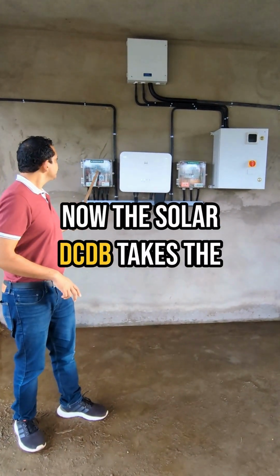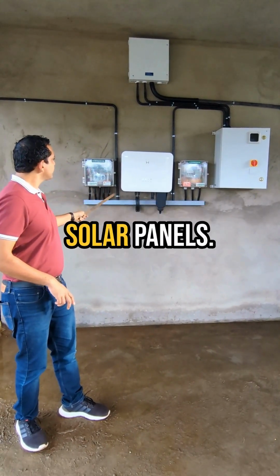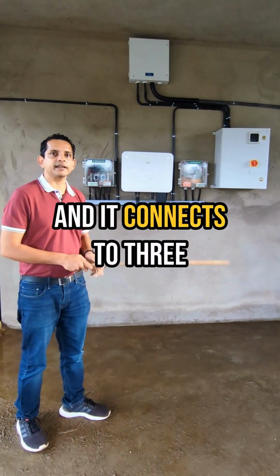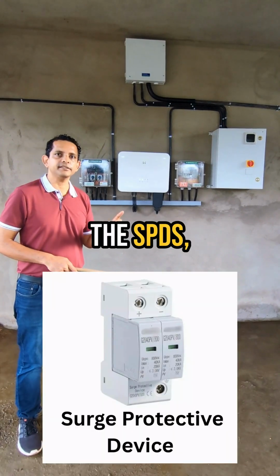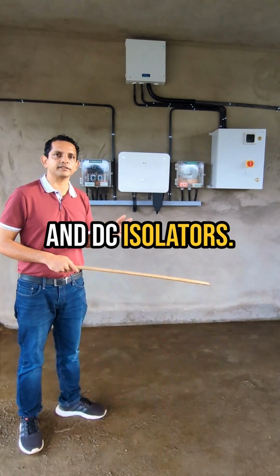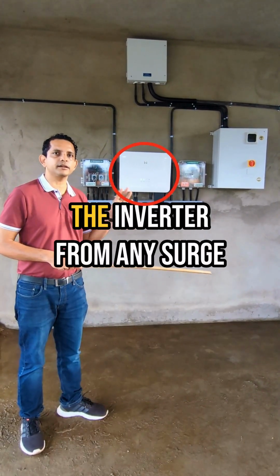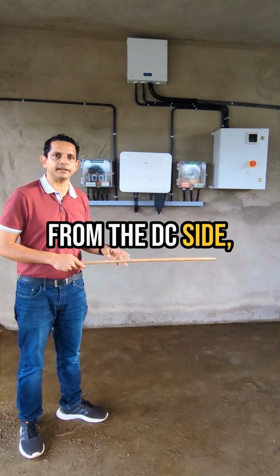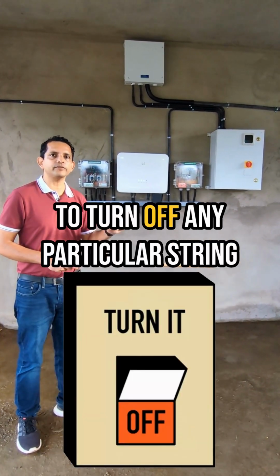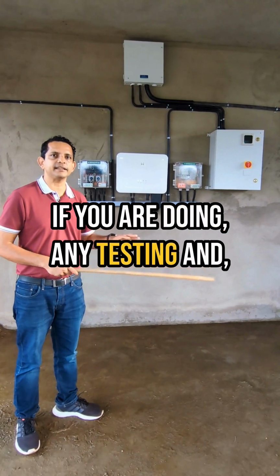The solar DCDB takes the power coming in from the solar panels. This goes to the DCDB and it connects to three components: the SPDs, DC fuses, and DC isolators. The SPDs and fuses protect the inverter from any surge from the DC side, and the isolators are required to turn off any particular string if you are doing any testing and troubleshooting.